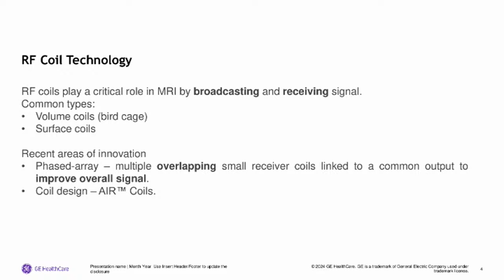So what are the recent technologies, the innovations that have occurred in the coil technology? We have the phased array technology, whereby we use multiple small coils that are overlapped so that they can improve the overall signal. So these are arrangements of small coils that work together to amplify the signal.